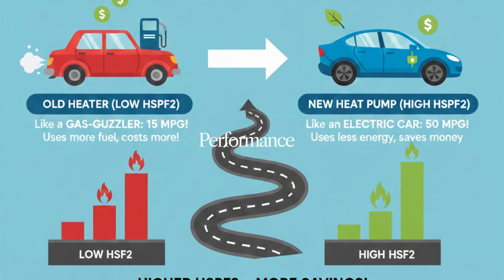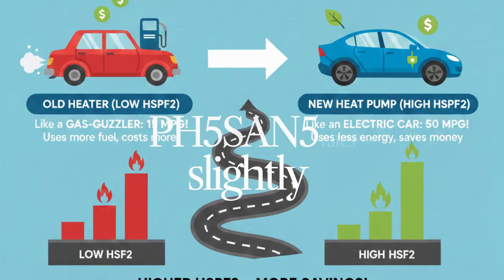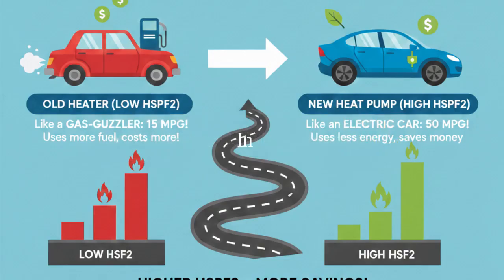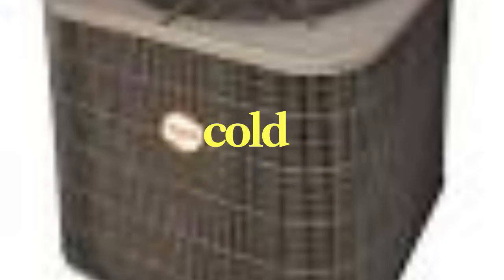Moving on to heating performance, we look at the Heating Seasonal Performance Factor, or HSPF. The Direct Comfort GSZH5 comes in with an HSPF rating of 7.8, while the PAN PH5SAN5 rates slightly higher at 8.1. In real-world winter operation, a higher HSPF rating means the unit squeezes more heat out of every kilowatt-hour of electricity it uses. That gives the PAN a slight edge in heating efficiency during cold weather, though both will deliver dependable cooling performance during the summer as well.